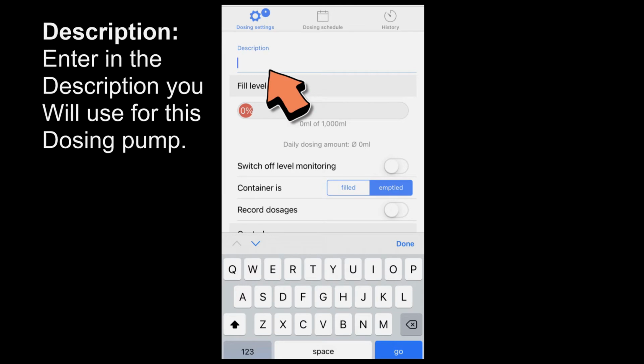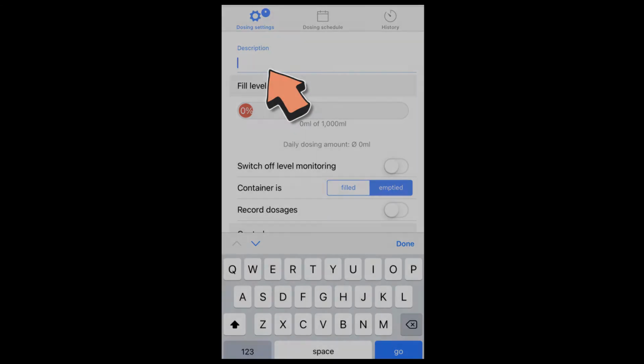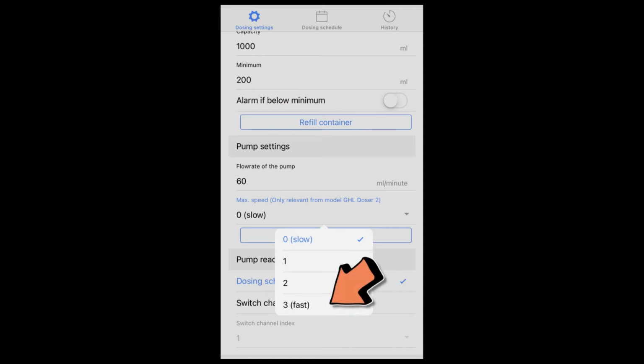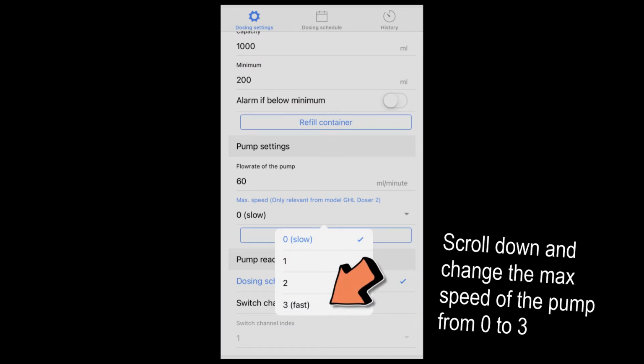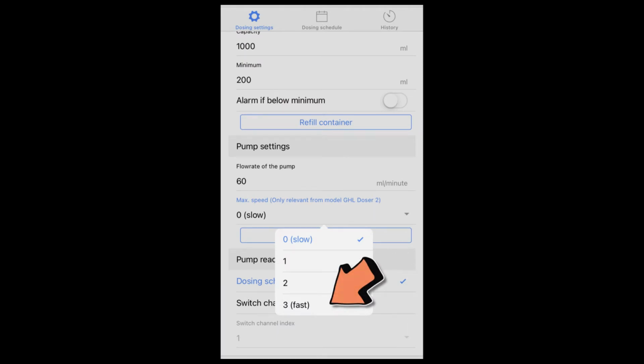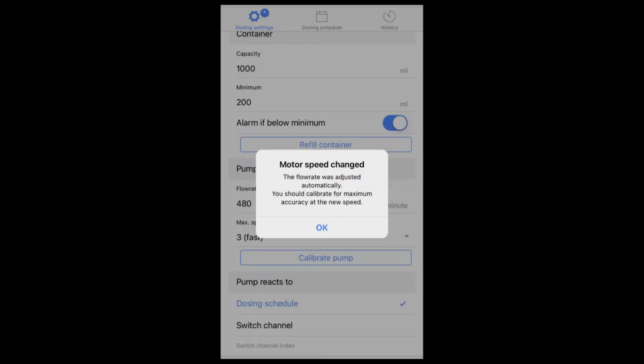Enter in a description that you wish to use for the dosing pump. For me, I entered in ion sample. Scroll down to the pump settings and change the max speed of the dosing pump from 0 to 3. A pop-up box will appear stating the motor speed has changed. Click OK, then choose the Save button.